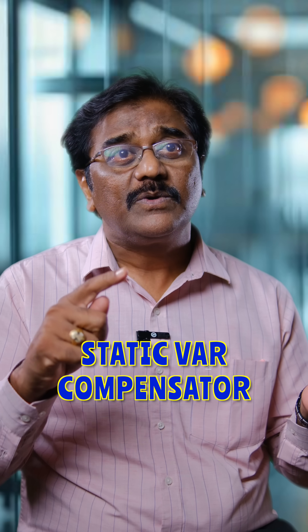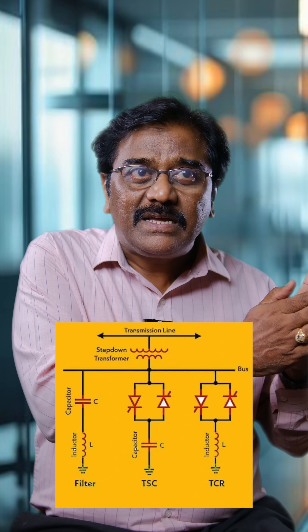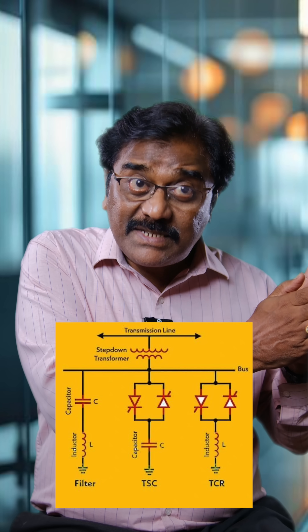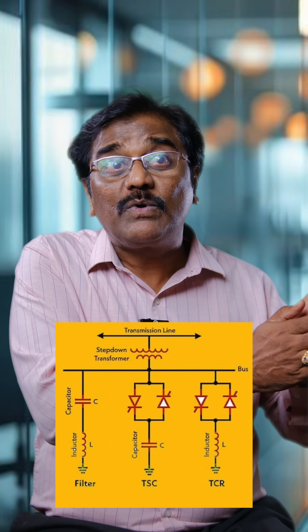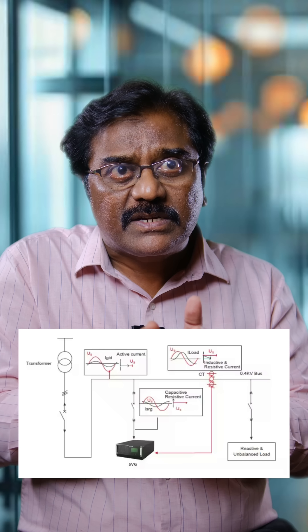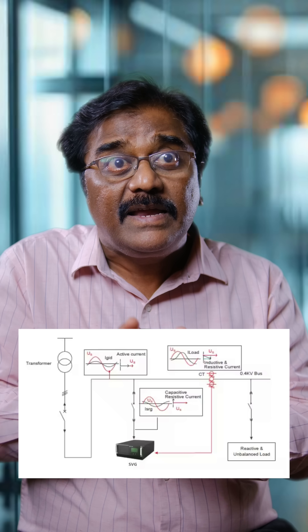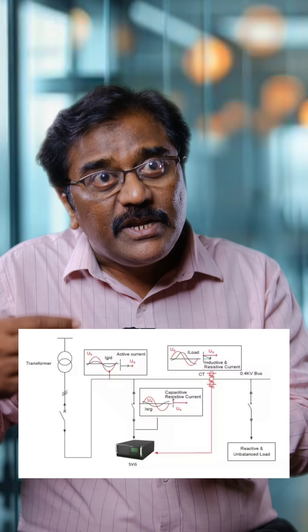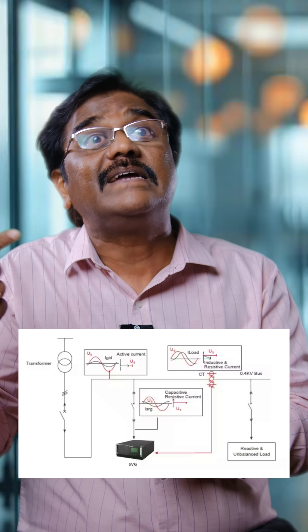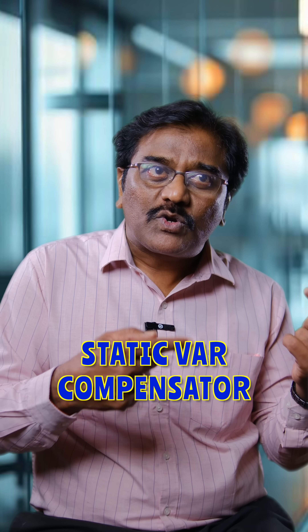When the power factor is in the lead direction, we generally have two solutions: one is the Static VAR Compensator and the other is the Static VAR Generator. When reactive compensation is required at a constant level and loads are very constant, we can go for the Static VAR Compensator. But when loads are continuously varying, highly dynamic, highly fluctuating, and non-linear, we need to go for the Static VAR Generator.